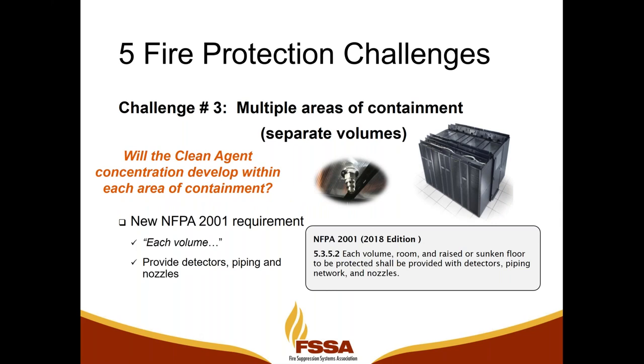Another question is, will that agent concentration develop within the area of containment? So if we've built a smaller volume inside the space, NFPA 2001, the standard for clean agent fire extinguishing systems, requires that each volume inside the protected space have detectors, piping, and nozzles. So now we're creating new volumes in the space that may not have detectors, piping, and nozzles, and today we do not have the data of whether or not that gas will get into that space without having nozzles inside of it, let alone detectors. If a fire starts inside that contained pod, do we get detection fast enough to activate the system and keep the fire as small as possible?